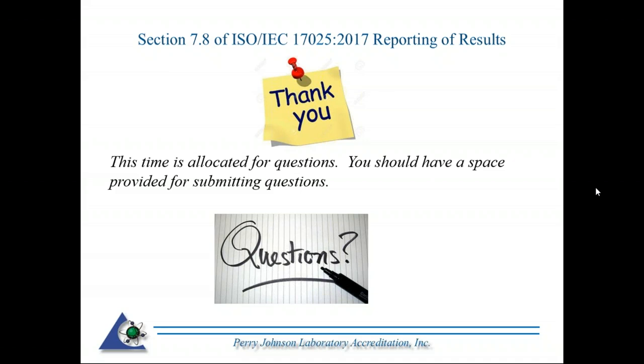The best thing I can refer you to in this case is we address this directly in PJLA's policy on measurement traceability, PL2, where we talk about in-house calibrations. So if you're going to perform them internally, as far as your accrediting body, we assess them just like an accredited type calibration. So you have to have proper procedure, you have to have the tools to do the job, your personnel has to be trained and competent, and the environmental criteria needs to be met.